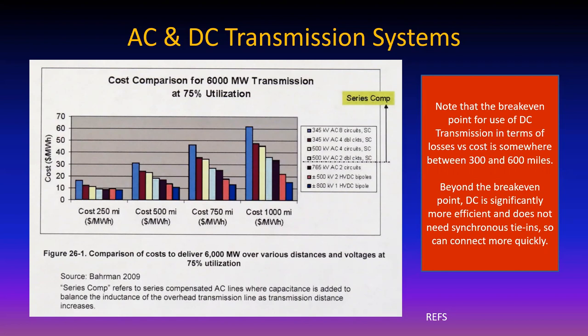The nice thing about DC is that there are two things that happen with AC: a long transmission line acts as an antenna and actually radiates power away from the line, and AC also crowds towards the surface of the conductor, called the skin depth of the conductor. DC, on the other hand, is uniform across the entire cross section. That means the same size conductor can carry a higher DC current than AC current, because it doesn't crowd the surface like AC does.